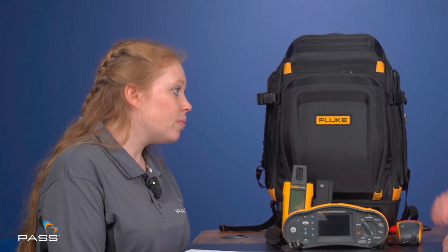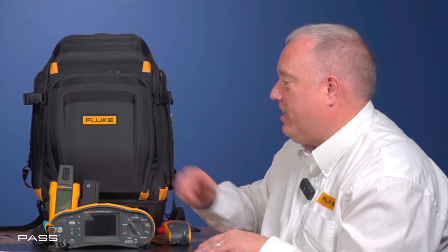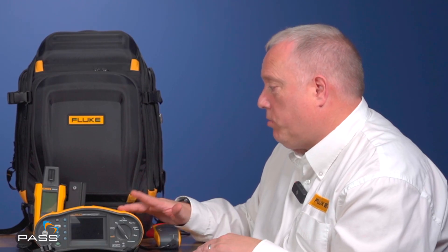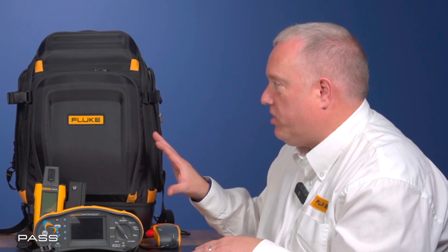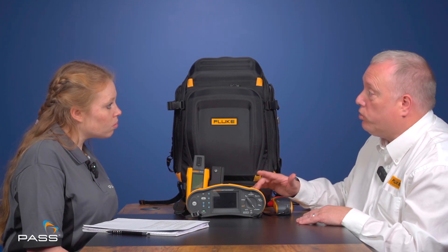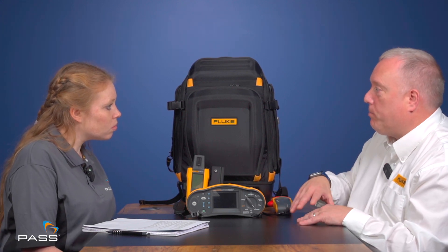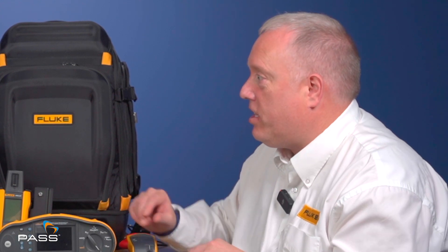The irradiance meter connects via Bluetooth; the power clamp connects via lead. The power clamp takes AC and DC measurements either side of the inverter, capturing KVA and KVAR values. As for why you should pick a Fluke solar kit — it offers a complete solution. The synchronicity between the Bluetooth irradiance meter, the clamp, and TrueTest software means it connects to other Fluke PAT testers and installation testers too, keeping information from your whole Fluke family of instruments in one location.